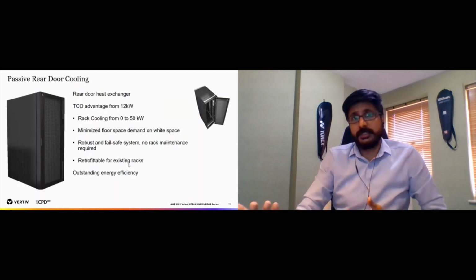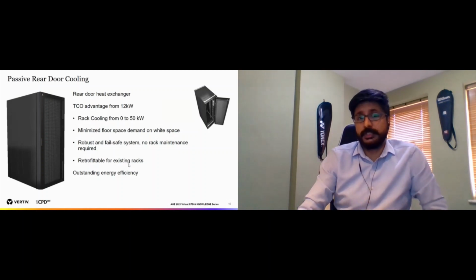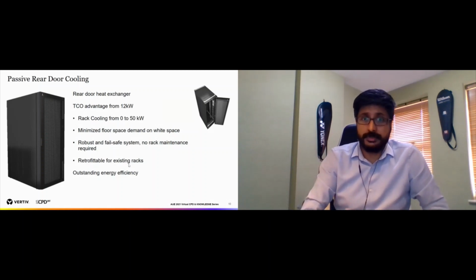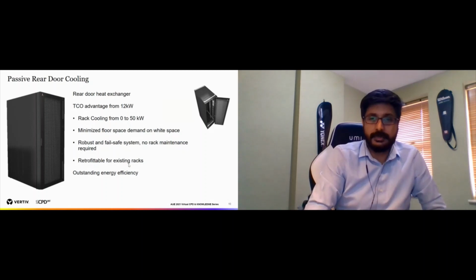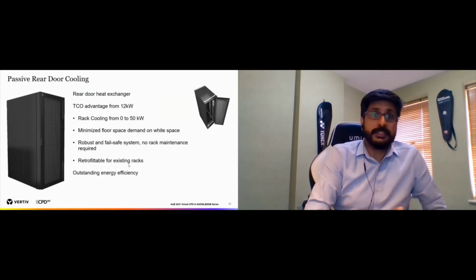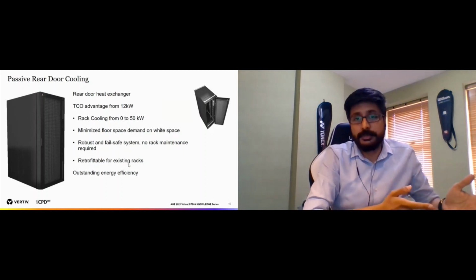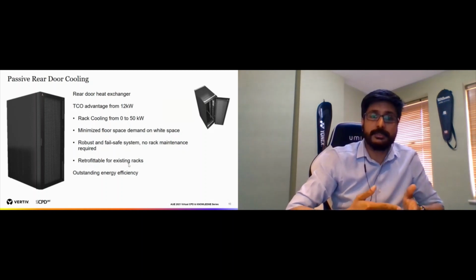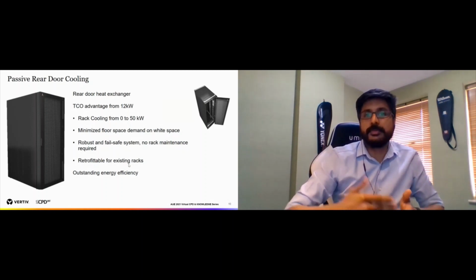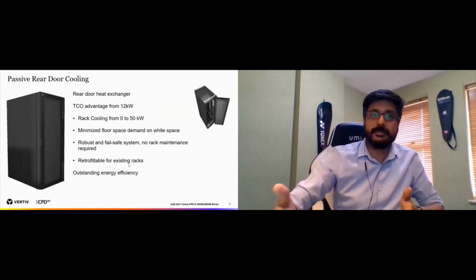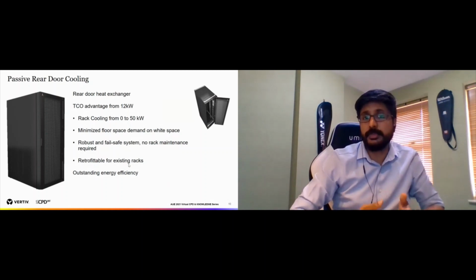We'll have a chiller that is sitting outside, and these can be free cooling chillers as well. So that gives you the free cooling efficiency, which means your PUE keeps improving. There's no additional space needed as well. There's a perimeter unit, and this can be connected to each and every rack. And because there's spare capacity on the passive cooling units, they can be working in an N+1 scenario as well.